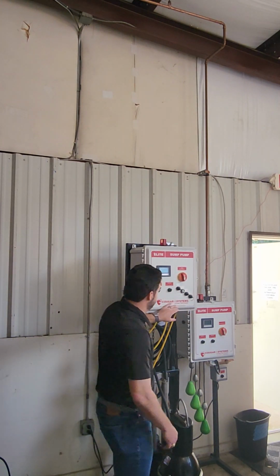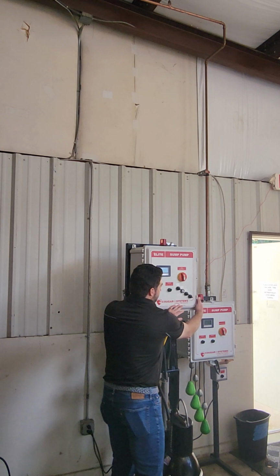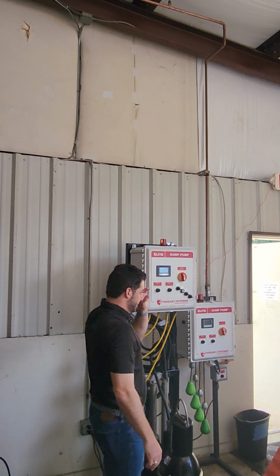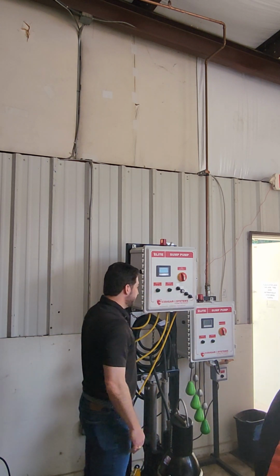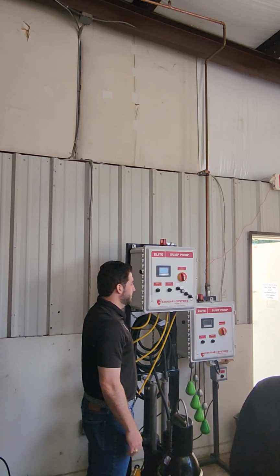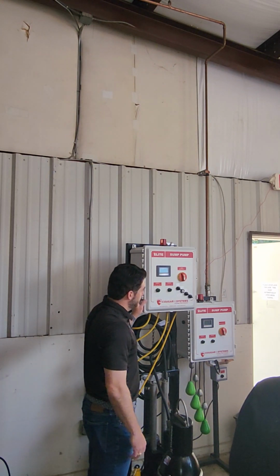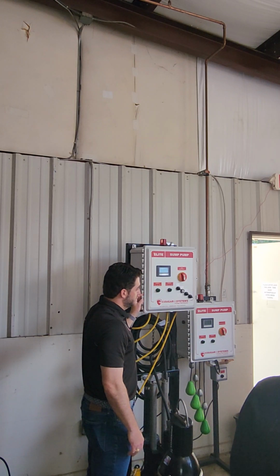The high check is the one you really have to worry about. And like I said, there could be a chance that it is leaking through and causing that alarm. But I've been in the field, I've been around people that fix them, cut it off, put it back together, and send it back to you. Because to me, it's just a dumb alarm.